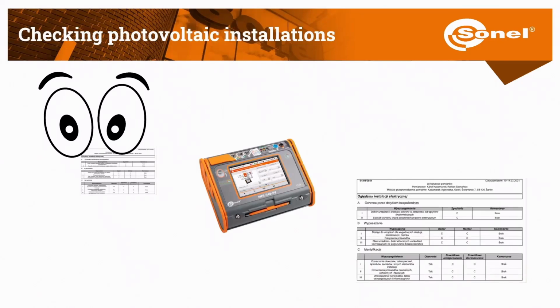The first survey on the photovoltaic installation is the visual check. Definitely this is one of the key parts of the installation. After the installation we have to check the whole installation as it is, checking all the MC4 connectors, checking for loose connections of the screws, and the connection of the bondings and the equipotential connector to the panels. This is the first thing we should do according to the standard.